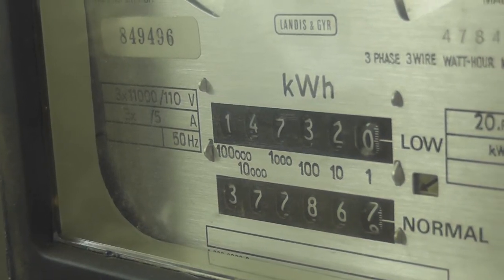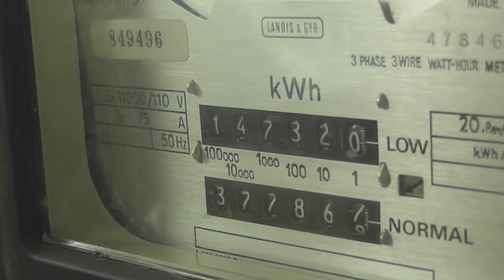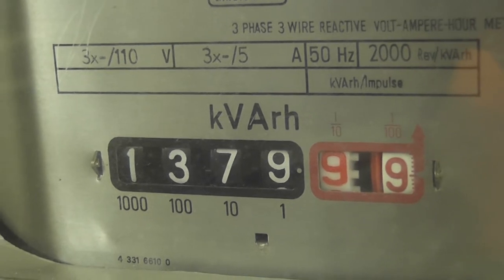Interesting to notice that the kilowatt hour meter register is geared for 11,000 to 110 — that's 2 units plus the actual multiplier. The kVArh registers are reading true values for 110 volts. Let's just put the camera on a tripod so we can get the click-over nicely.